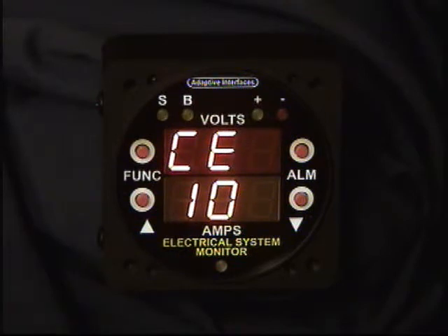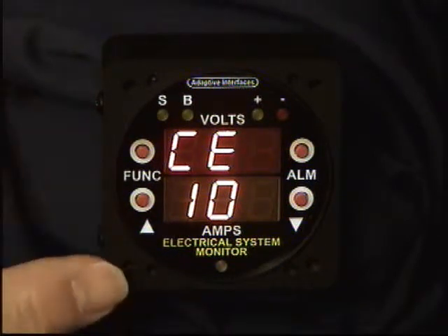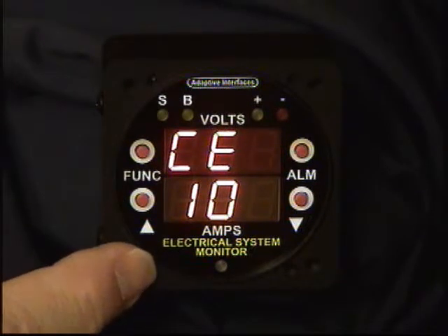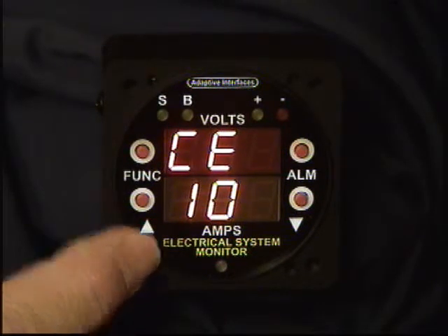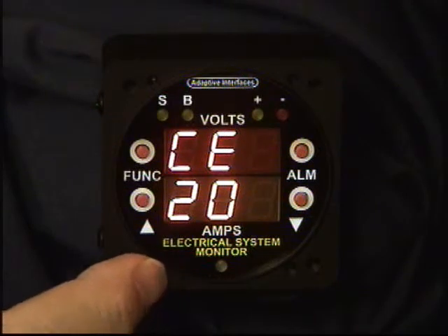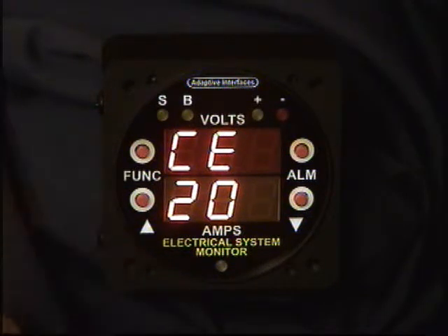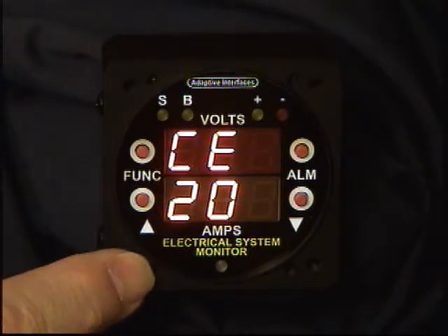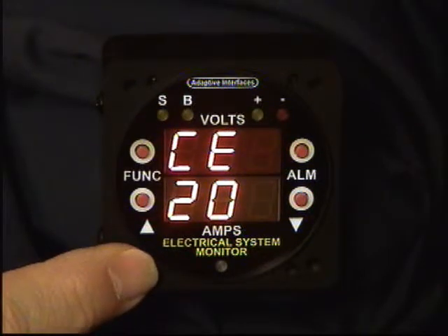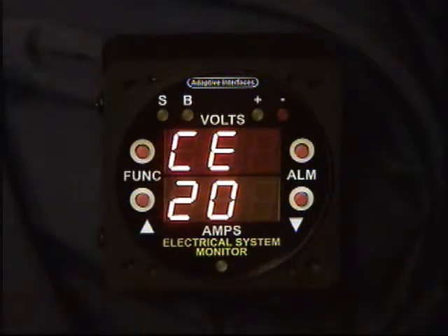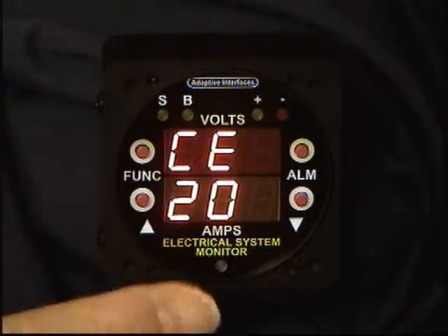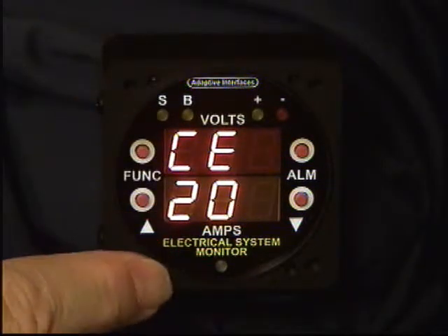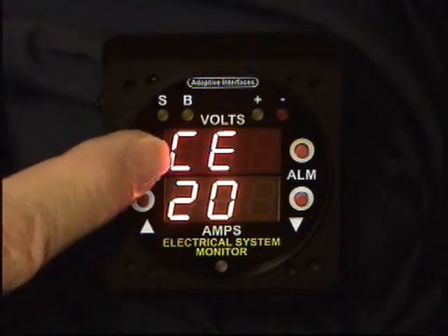The first set of calibration points is for the voltmeter. The calibration data points can be set at 10 volts and at 20 volts. This will set up and calibrate the voltmeter inside the instrument. Again, if you don't have a precise voltage source, it's suggested that you don't mess with this calibration menu at all. But it is available if you need to use it.